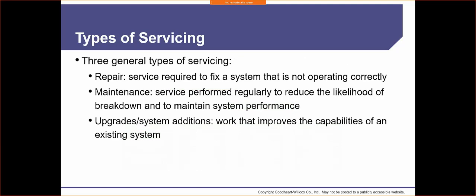So there's three different types of service work. We're talking about repair. Somebody calls and says, hey, my heat's not kicking on. So you go in and you troubleshoot and you find that the blower motor's not working. So we would replace that blower motor, and that'd be considered repair. Maintenance is performed regularly to reduce the likelihood of a breakdown. Like I said, it's like changing the oil in your car.